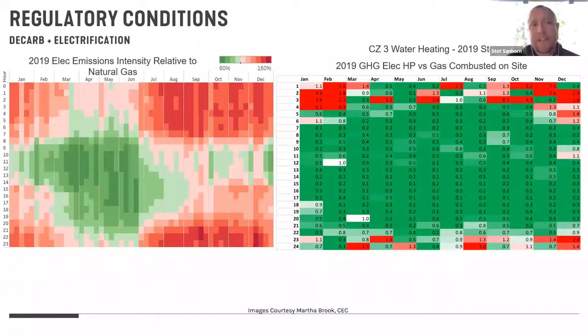So in the image on the left, using electric resistance, I can still have a lower carbon footprint essentially between 9 a.m. and say 2 p.m., or all the way up until maybe about 4 or 5 p.m. For several months of the year, I can actually have lower emissions using electric resistance heat, which I would never promote. I would say, don't do that. And that's one of the issues they're having in Texas right now, quite a bit of use of electric resistance heat. Compare that graph on the left to the graph on the right. This is if I use a heat pump with a COP of just under 3 to do the same task, whether it's space heating or domestic hot water production or service hot water.